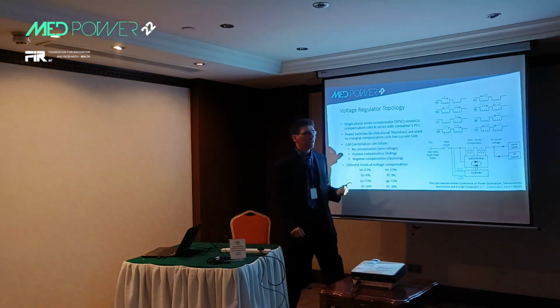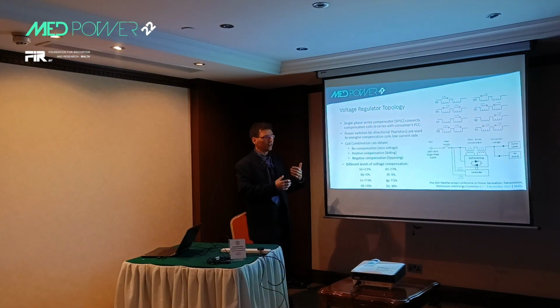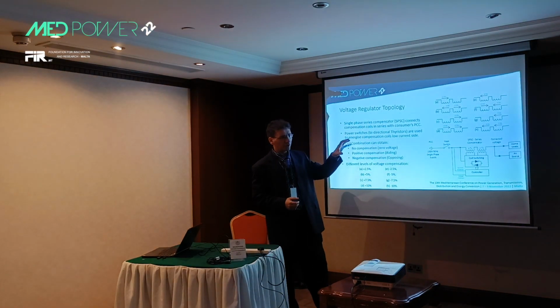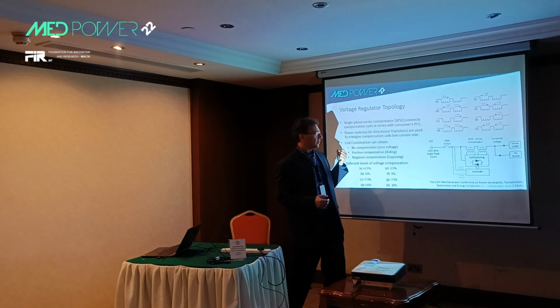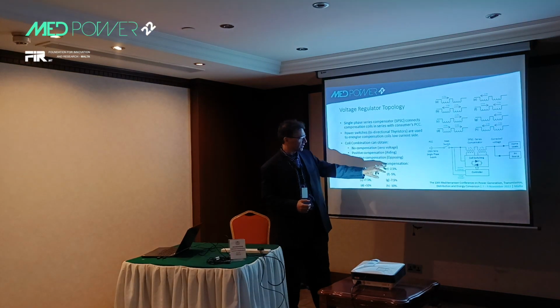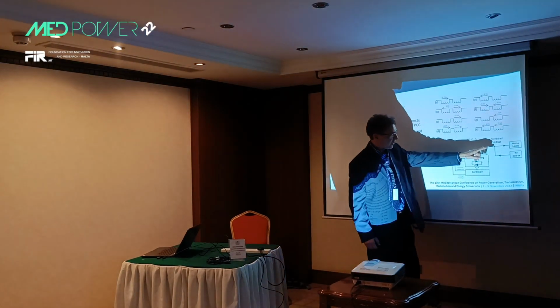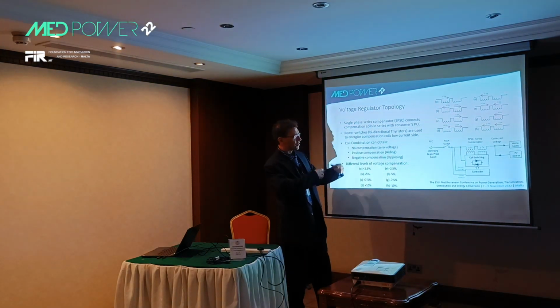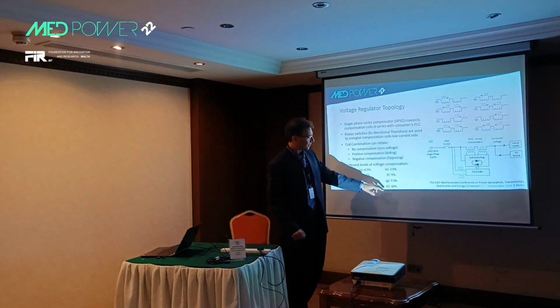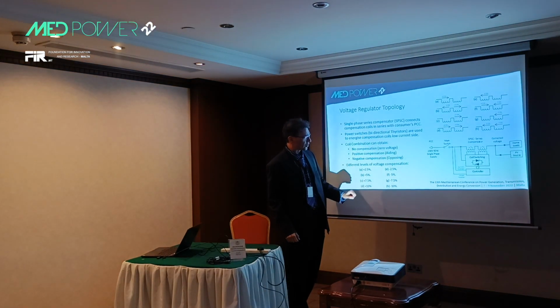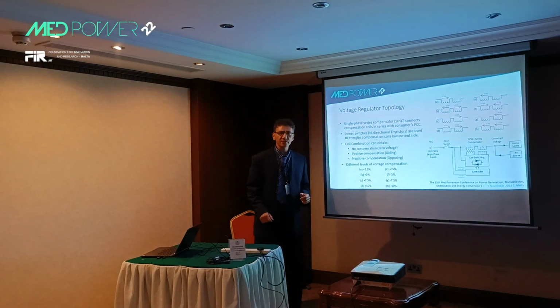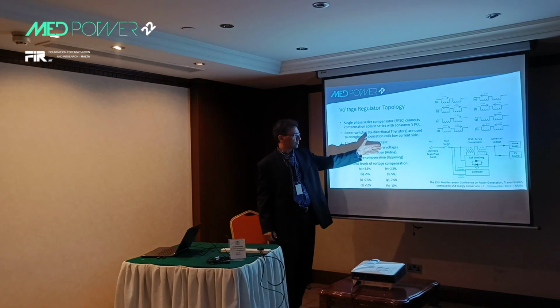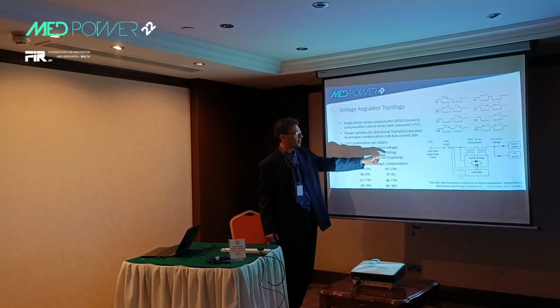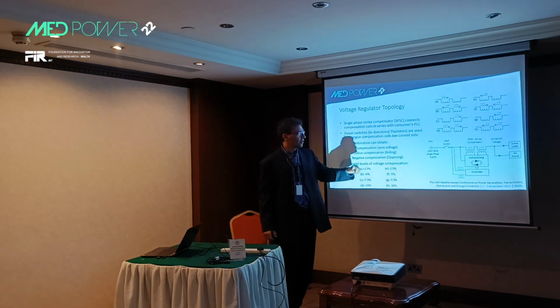On the other hand, if the PVs are generating a lot of energy into the grid and our point of common coupling, the supply voltage, is very high, then we want to decrease the voltage seen by the consumer. So what we'll do is we will switch the coils in the reverse direction, as shown over here, and like that we can achieve steps from minus 2.5 up to 10%. Okay, so you've got no compensation at all, aiding, that is increasing, or opposing.